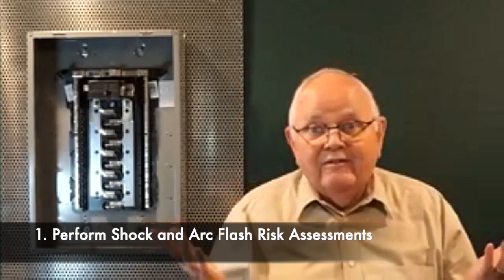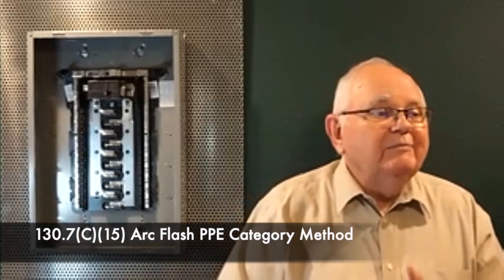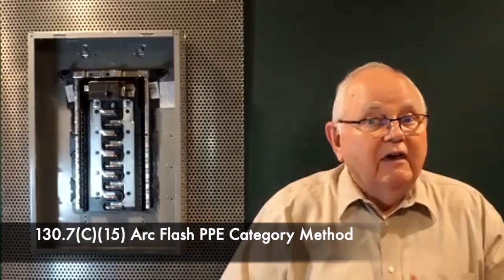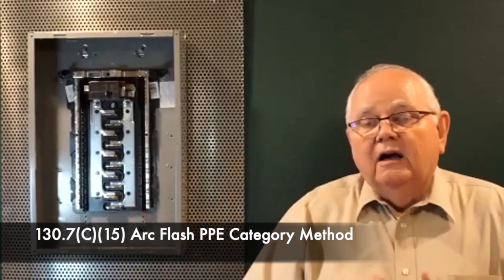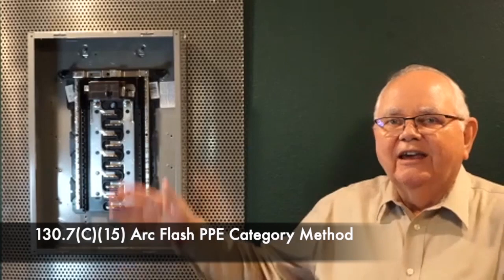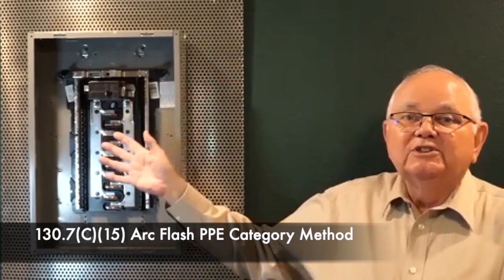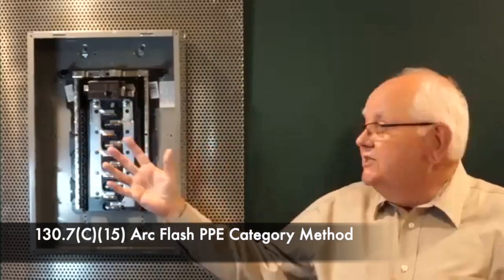That's what we don't want to have happen to us. So the purpose of the shock risk assessment, we identify the hazard. We look at the label on the equipment. If you don't have the label on your equipment, go into Article 130 of NFPA 70E, and you'll find something called the PPE category method. And that will solve the problem for you as to how you can determine what the potential arc flash incident energy might be coming out of a panel like this if you haven't yet done an incident energy analysis.